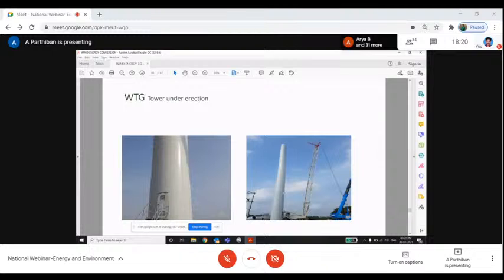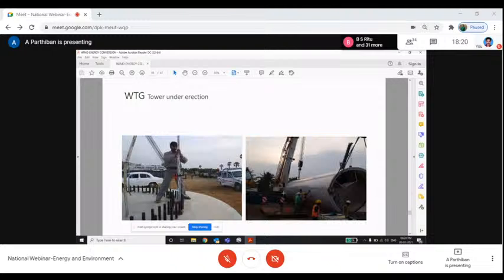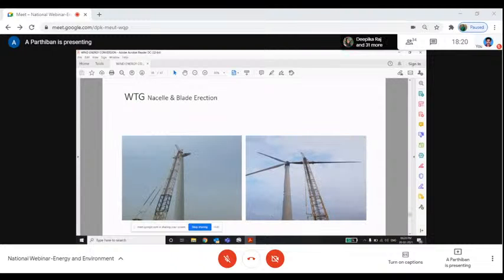For example, for this 2 megawatt tower, we need to use a 600 metric ton crane to install the total WTG. These 4 tower sections will be installed one by one. And finally, we will install the nacelle and blades. These are all the photos of how the crane is installing the nacelle and rotor.